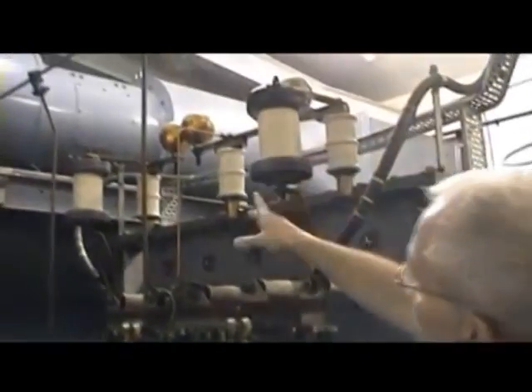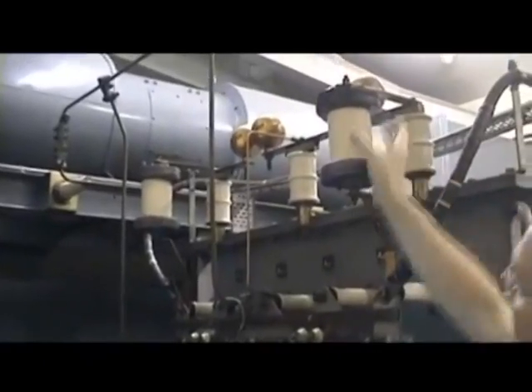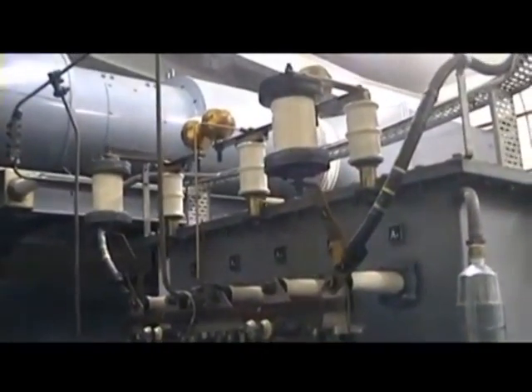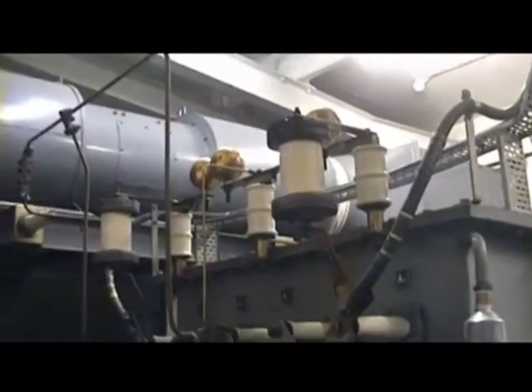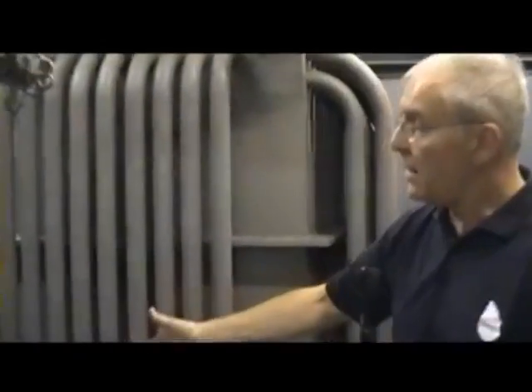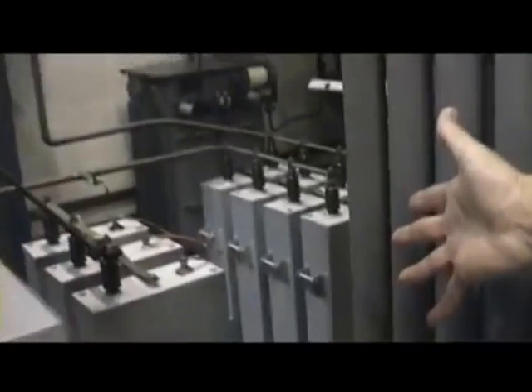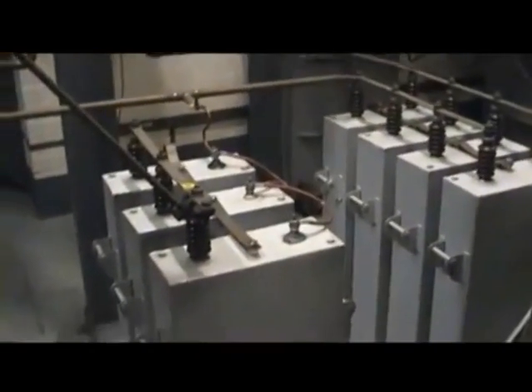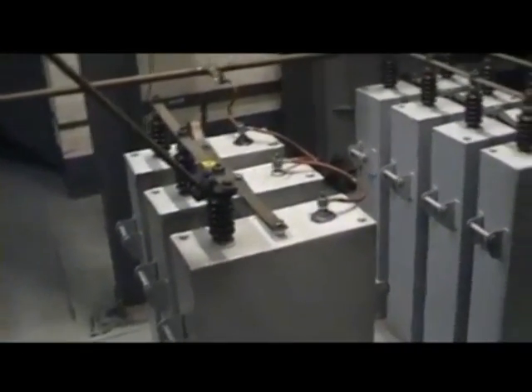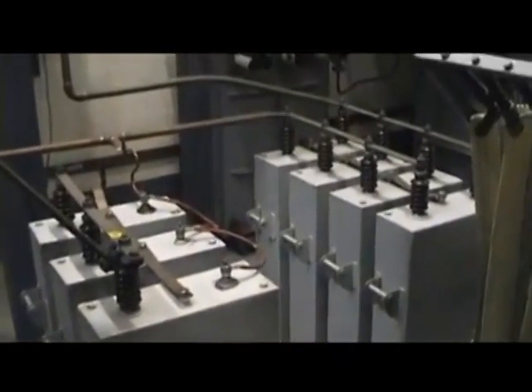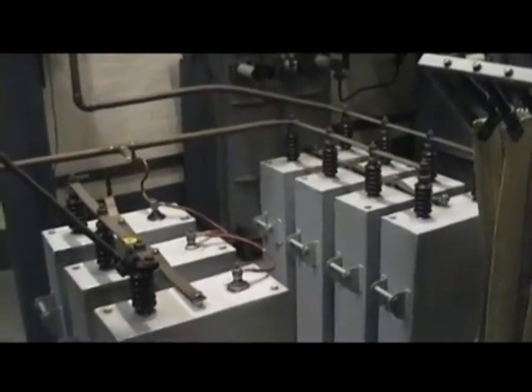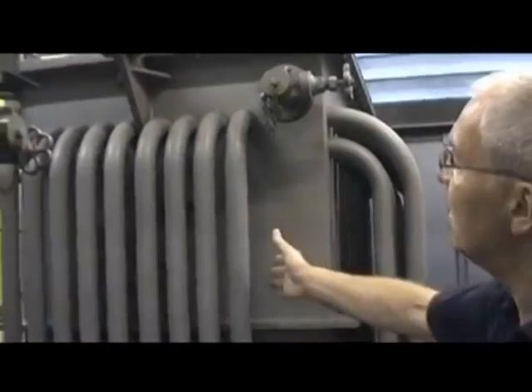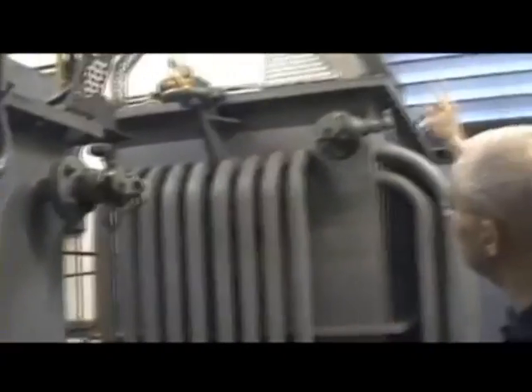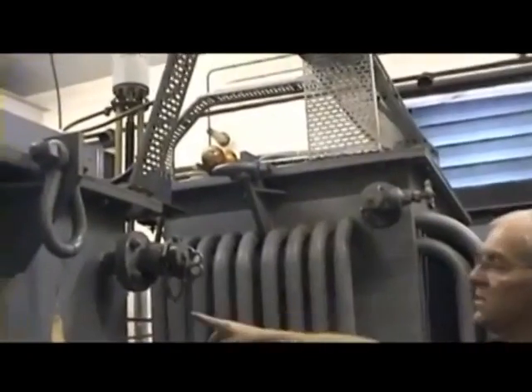Various bits of protection here: ball gaps for flashovers, and Metrosils, which are like voltage-controlled resistors. Big voltage, it'll just shatter, but it will save the windings in the transformer. Just looking through here, we can see 3 large capacitors on the floor, a set of 3. These are modulation blocking capacitors, and are from one connection of the mod transformer to earth. The other connection up to the HT line is made by this reactor, which is here. It's always a reactor in the States, a choke in the UK. This is a low frequency reactor. It allows us to pass the DC through the reactor to the secondary of the mod transformer.